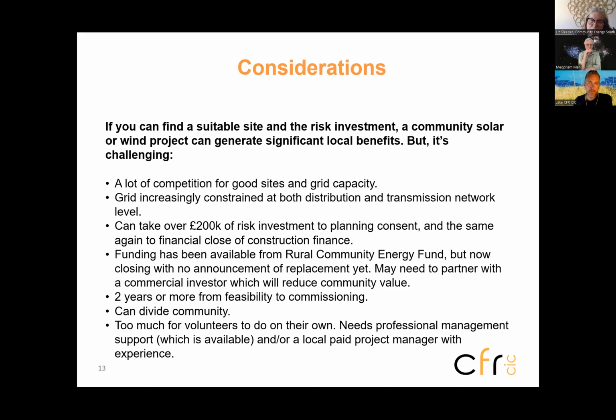So considerations: there's a lot of competition for sites. You're up against well-funded, well-resourced, experienced commercial developers, and that competition is primarily for grid capacity. The grid is getting increasingly constrained, not just at distribution level but also at transmission level. The shift to subsidy-free has meant developers are looking for much larger schemes - schemes too big to connect at the distribution network, the 11 and 33,000 volt network - so they're connecting directly into the 132,000 volt transmission network. Now we have the grid being squeezed from two directions: the accumulation of projects connecting at distribution level, but also from the top down with very large solar and battery schemes connecting directly at transmission level.